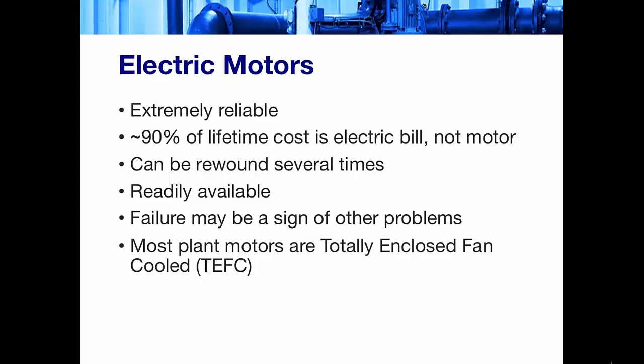Electric motors are very standardized and are very readily available. There is NEMA, which I can't think of what that stands for. They have different frame sizes, different horsepower ratings, and electric motors for most sizes and applications are kind of a commodity product. It's important to note that electric motor failure may actually be a sign of other problems. The motor itself may have been fine, but you had poor power quality, or it was connected poorly, and just because an electric motor fails, the actual cause of the problem may not be the electric motor itself.